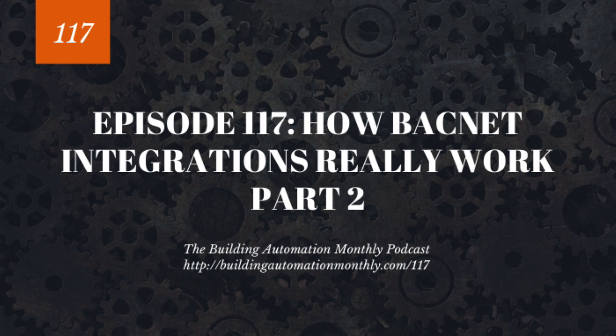Well, as you learn how the controller then gets rid of the token and passes it on to the next controller, it normally goes in sequential order of the addresses. That's why if you address your stuff 1, 2, 3, 4 in sequential order down the trunk, it makes your network a little bit faster. It also makes it a lot easier to troubleshoot, because the beauty of BACnet is that even if a controller goes down, typically the trunk will keep communicating.